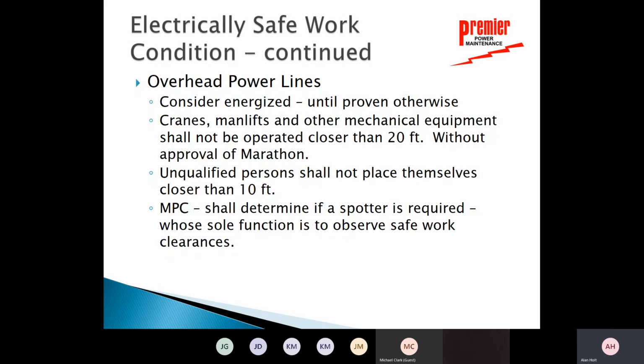So they have some other rules. Some of them are a little different than what we're accustomed to, but it says cranes, man lifts, and other mechanical equipment shall not be operated closer than 20 feet without approval of Marathon. Typically, our standard has always been 10 feet, so they're a little more stringent. So basically you can't get equipment within 20 feet of overhead power lines. Unqualified persons shall never place themselves any closer than 10 feet. Basically for us, I would think that we would want to try to avoid being any closer than 10 feet to an overhead power line ourselves.